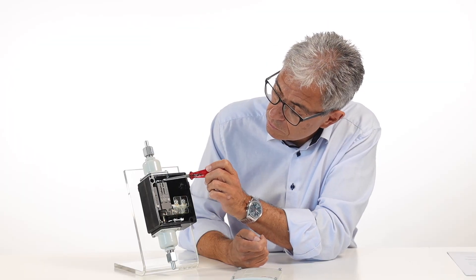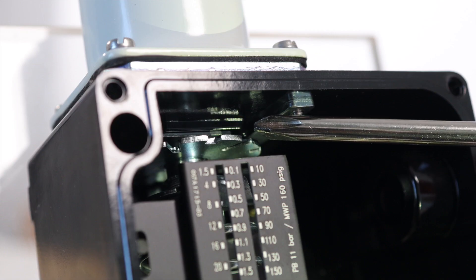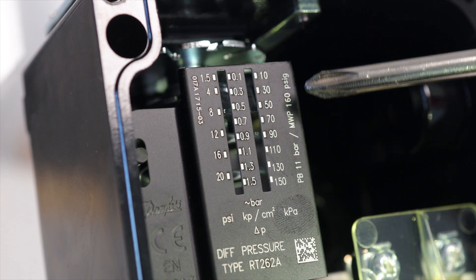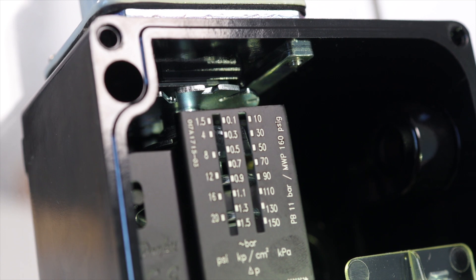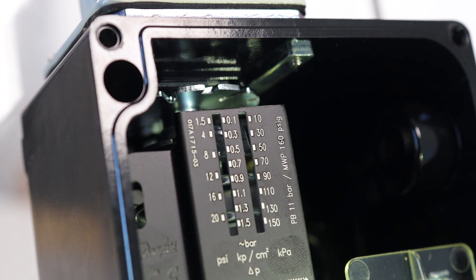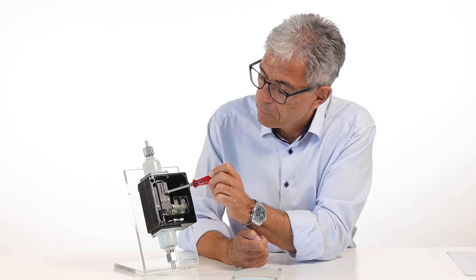Here, you can set the required differential pressure with the setting disk while at the same time read the scale. RT262A covers the range from 0.1 to 1.5 bar. In this example, we'll set the level to 0.5 bar.